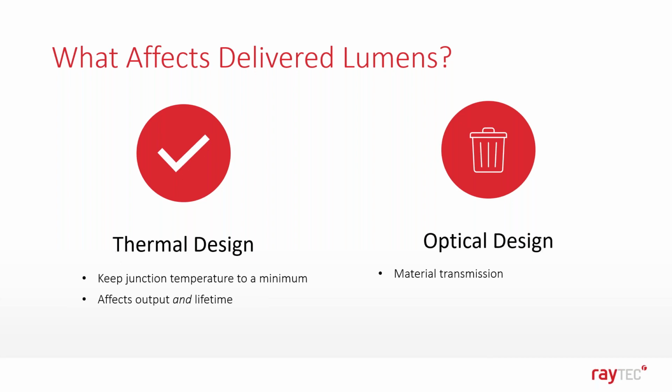So you might think that the ideal luminaire would have no secondary optics, and this keeps the transmission to a maximum. Now this can be true to a point, but light is only useful if it is directed to the task where it is needed. This is where a good secondary optic comes in. Secondary optics also have the added benefit of reducing total internal reflection within the luminaire and reduces other light loss and glare due to emission at high angles.